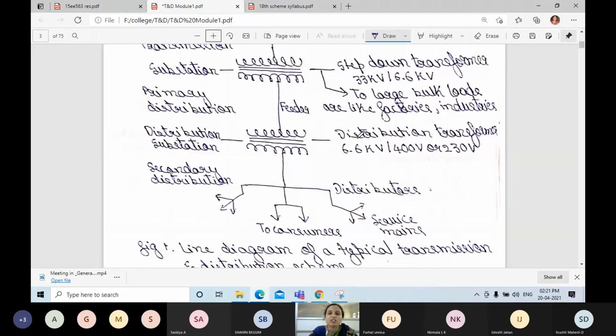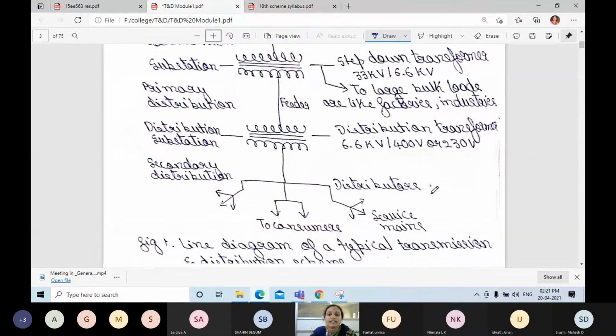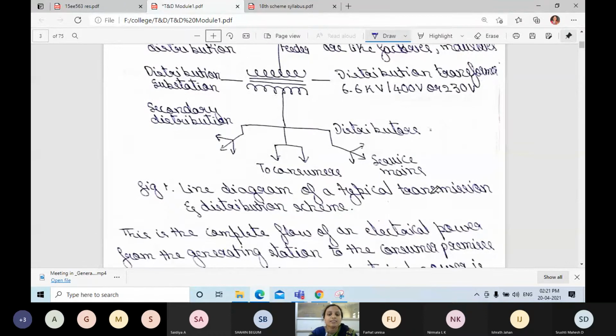Distribution substation: 6.6 kV to 400 volts or 230 volts. This is primary distribution. Secondary distribution is from 400 volts, and this is given to consumers. This is the line diagram of a typical transmission and distribution scheme.